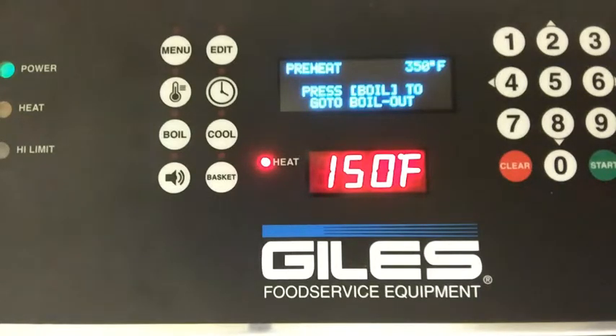The thing about the ILS is if you have a power issue, a lot of times when power comes up, it doesn't come up at full power. So this keeps from burning up contactor coils. It also keeps the unit from coming on and starting to heat. Perhaps you were doing a boil out and you've dropped all your oil. There's no oil in the vat. You don't want it to turn around and just go ahead and start heating. It could cause a fire. So for safety reasons and for equipment safety reasons, you would want to go ahead and use the ILS. All of Giles fryers will ship from the factory with the ILS turned on.